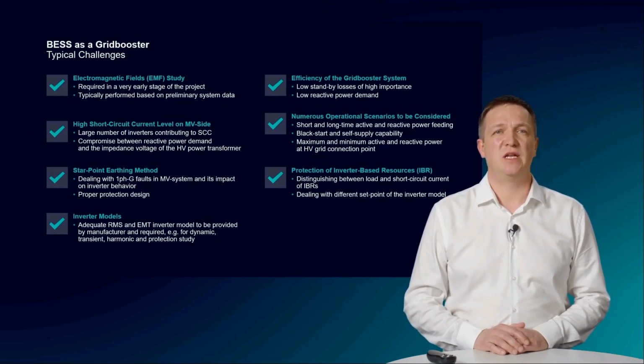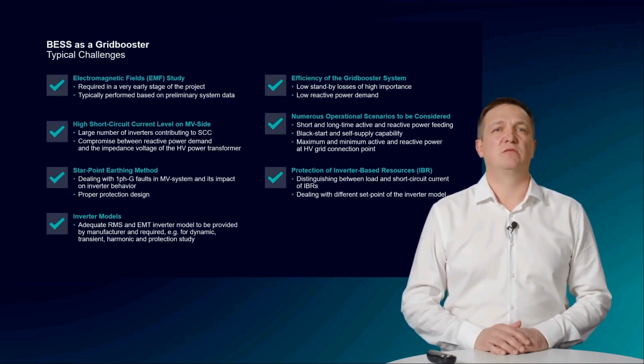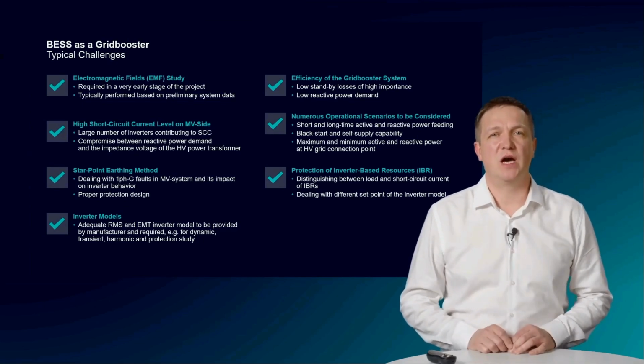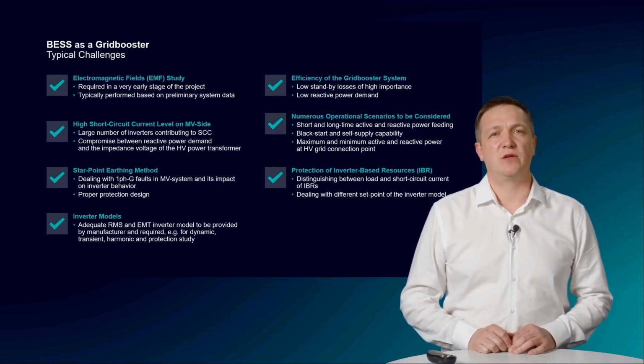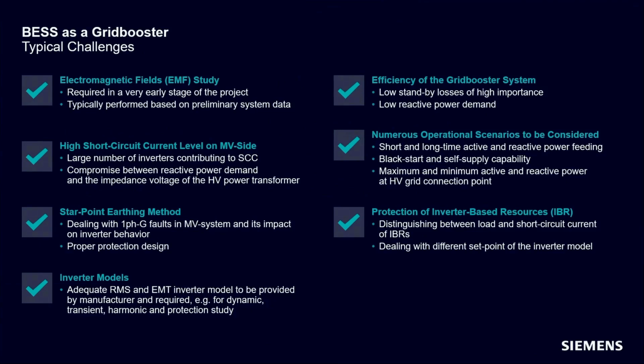Another challenge is dealing with the maximum available short-circuit currents in the medium voltage system, considering different operational scenarios, voltage levels of the high voltage system, etc. During three-phase short-circuit currents, the medium voltage switchgear is exposed to short-circuit current flowing from the high voltage grid, plus the short-circuit current coming, of course, from the inverters themselves. The sum of both short-circuit current contributions must not exceed the maximum permissible short-circuit withstand capability of the switchgear. When exceeding the limits, one can hardly limit the current coming from the inverters.